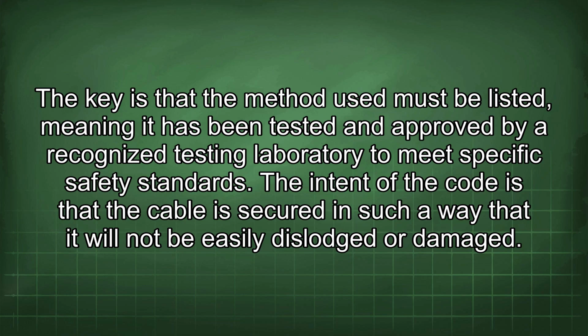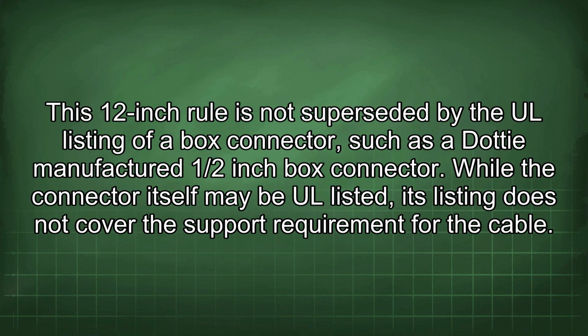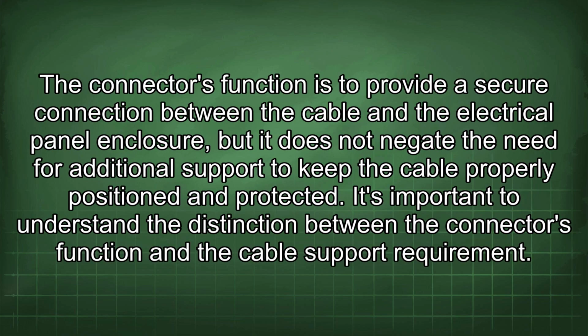easily dislodged or damaged. This 12-inch rule is not superseded by the UL listing of a box connector, such as a Dottie manufactured 1/2-inch box connector. While the connector itself may be UL listed, its listing does not cover the support requirement for the cable. The connector's function is to provide a secure connection between the cable and the electrical panel enclosure, but it does not negate the need for additional support to keep the cable properly positioned and protected.